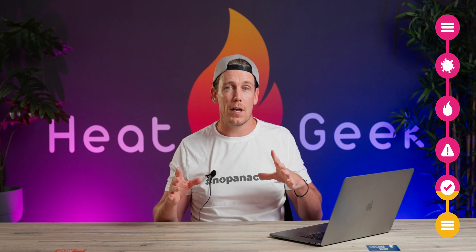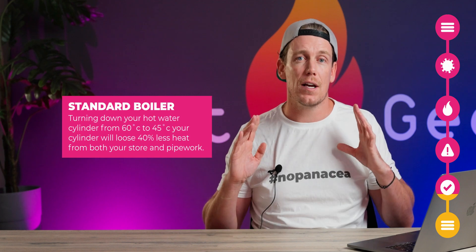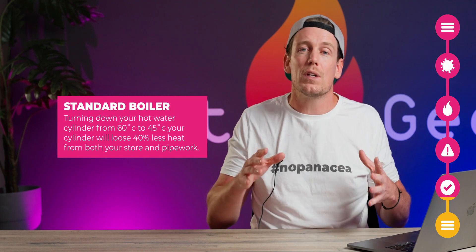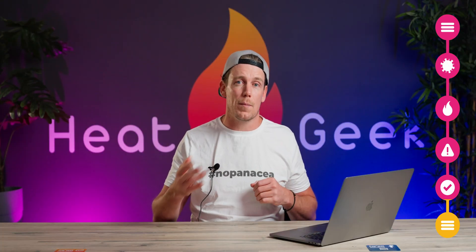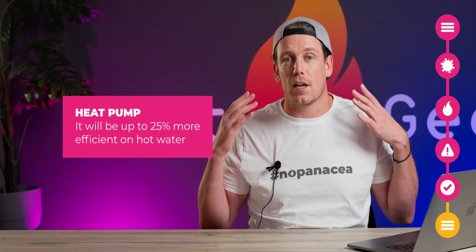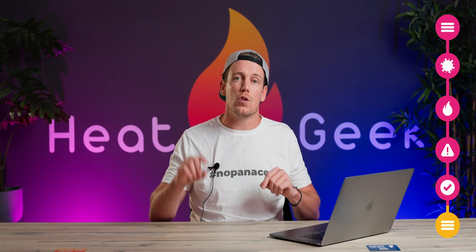So what does this do for your efficiency? If you have a combination boiler, turning down from 60 degrees to 40 degrees could make your boiler 10% more efficient on hot water production. If you have a standard boiler with a cylinder, turning down your hot water from 60 to 45 degrees means your cylinder will lose 40% less heat from the cylinder and the pipework, your heat source will cycle less as the cylinder cool-down is slower, and your condensing gas boiler could be 10% more efficient. And if you have a heat pump it will be up to 25% more efficient on hot water. If you have a slightly older heat pump that requires an immersion for anti-Legionella cycles, that will help prevent that immersion turning on at a COP of one, saving yet more energy. All of this will directly reduce your monthly bills.